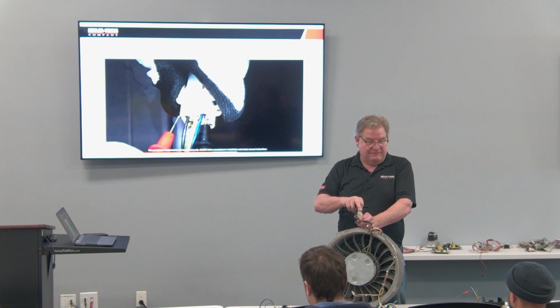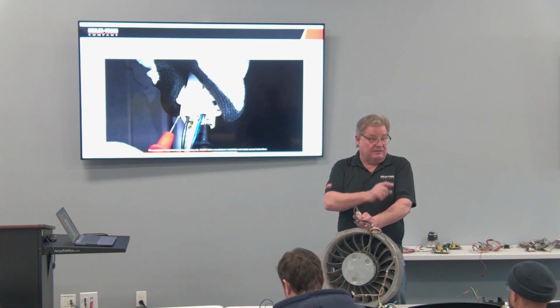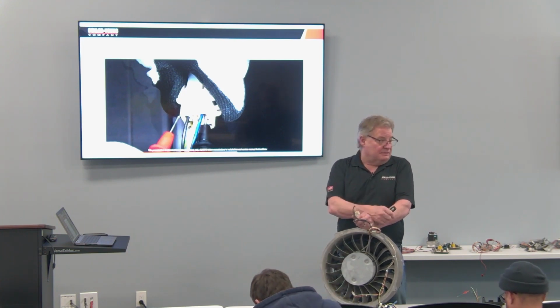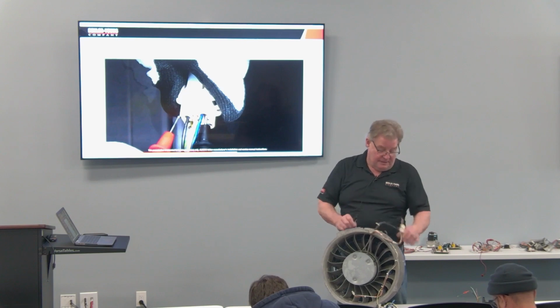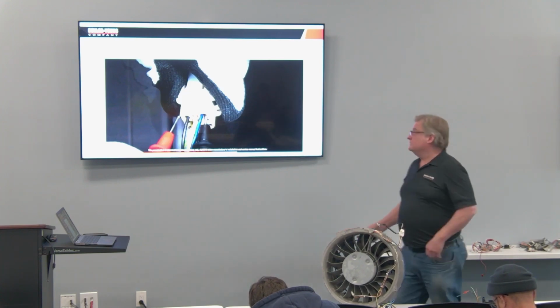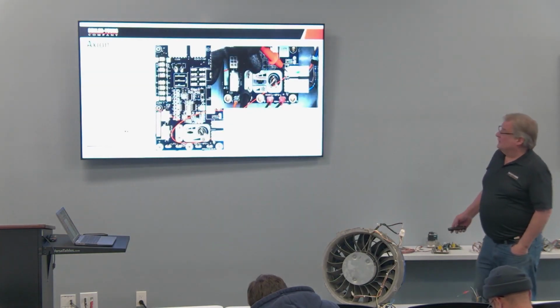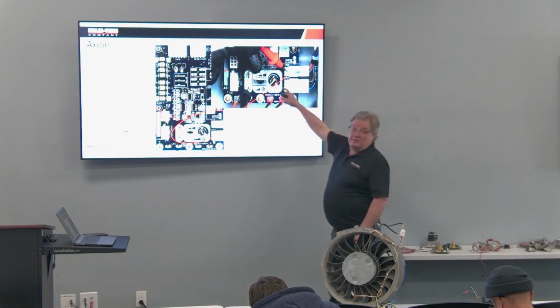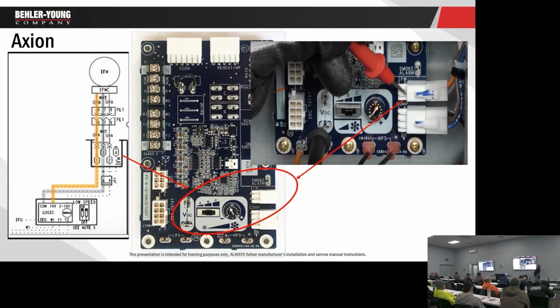But if I have 9 volts going to that gray, or whatever that dial is set at, the motor should be running. Okay, so it's pretty simple to test. I can actually do it at the board as well. So you can see the orange wire and the gray wire. Remember, negative is the bottom, so that would be white. So I can put my meter on negative. I can check the orange, I can check the gray.